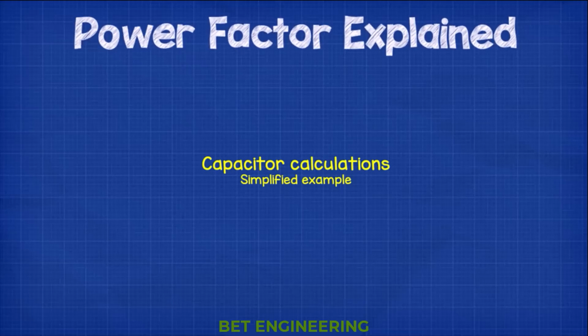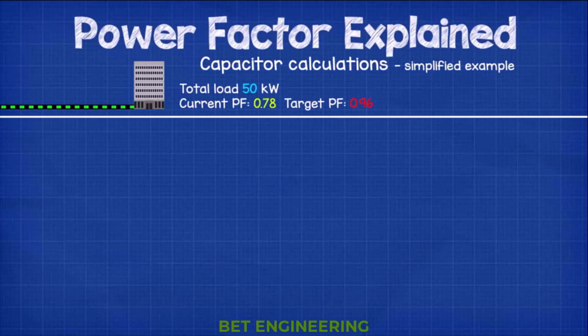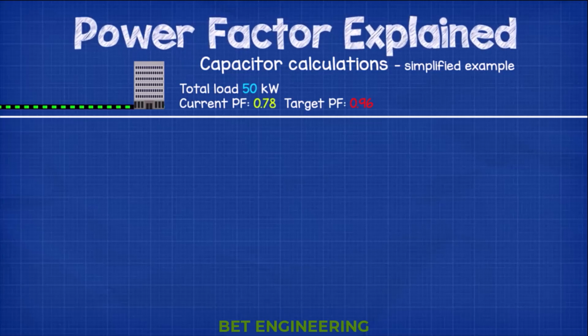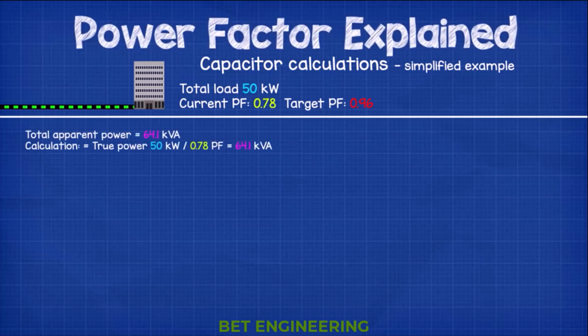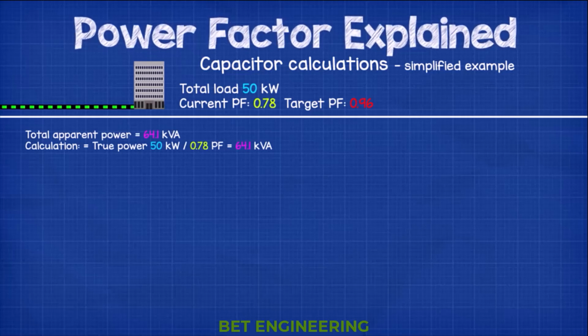Capacitor calculations for power factor correction. Let's look at a simplified example of calculating the size of a capacitor to improve the power factor of a load. The building has a 3-phase power supply and has a total load of 50 kilowatts of work. It also has a power factor of 0.78, but we want it to be 0.96 to avoid penalty charges. Currently, the building has a total apparent power, or kVA value, of 64.1 kVA, and we find that by just dividing the kilowatts, 50 kilowatts, by the power factor of 0.78.